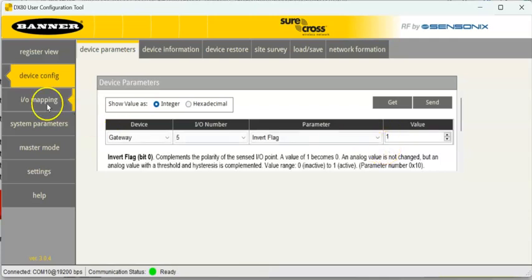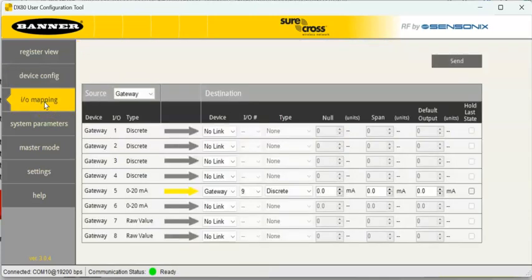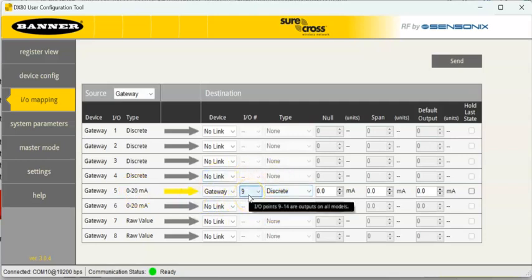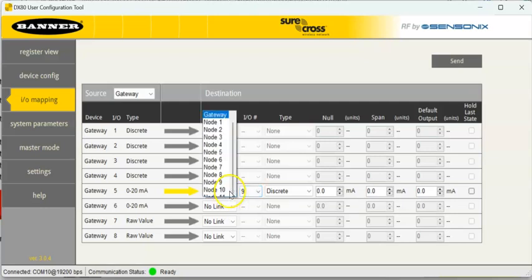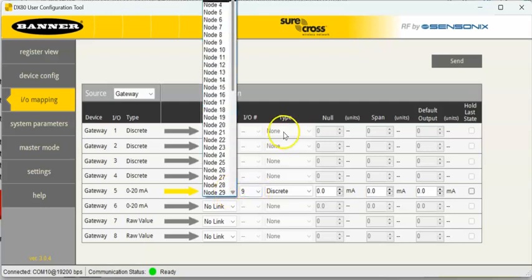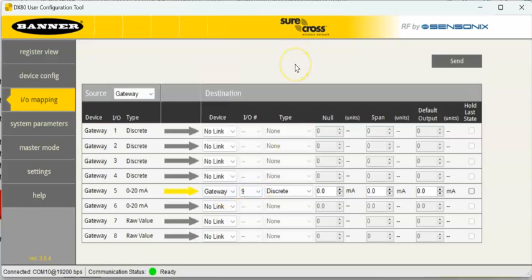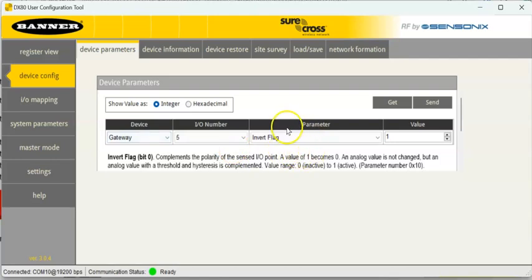The other final part of that is under IO mapping. This is old school. Under IO mapping, I'm going to output, or I'm going to link the input to an output. Now, I have it linked to the gateway here, but I could also link it to node one, node two, or three, or whatever, to the same IO point. But same thing. So, I have to link that IO. This is going to sound weird because I'm taking an analog input, and I'm linking it to an output. But this gets controlled based on these parameters we did here.